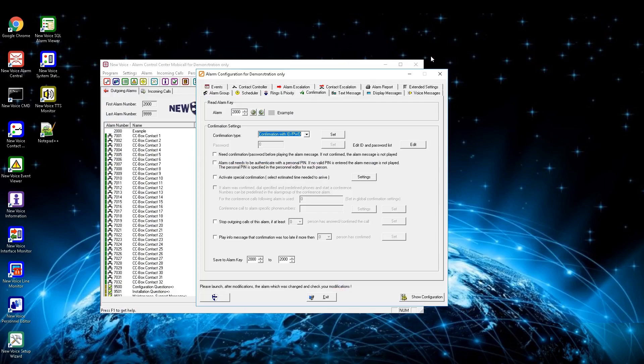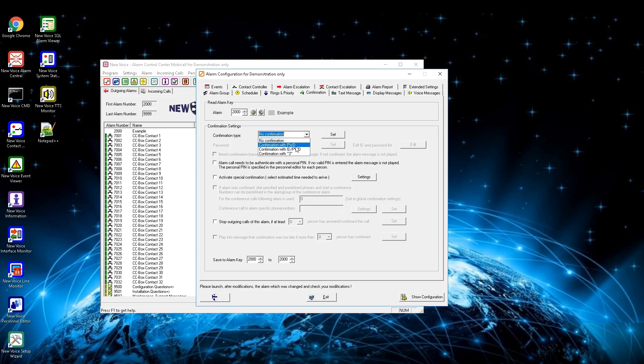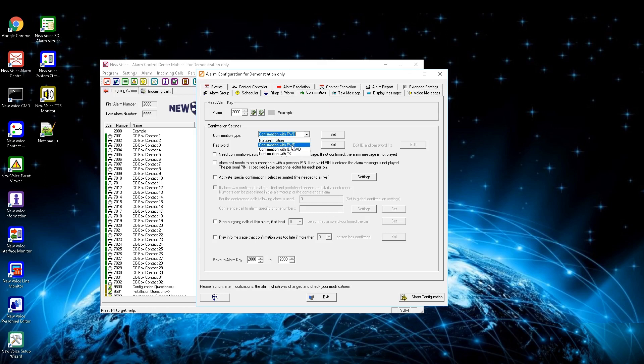In the confirmation settings tab you can define how the user needs to confirm the alarm, to make sure somebody receives it. The first drop-down menu lets you define if you want to confirm with password, confirm with ID and password, or confirm with key 3. By activating confirm with password the grayed-out password field becomes available. By activating confirm with ID and password you have the option to edit the ID and password list where you enter them globally. By activating confirmation with key 3, the user needs to press key 3 to confirm the alarm.